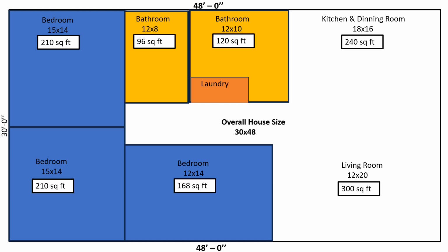Now, in doing this, I want to show you the numbers though. I want to go back just a second, without trying to be too confusing. Let's say you're that guy that says, well, I can get a better deal on a 2.5-ton system. I just want you to see what these numbers are going to look like. If I was to go with a 2.5-ton, well, that's 1,000 CFMs divided by the 1440, and you would get a 0.69. And this would be your numbers if you looked at it.